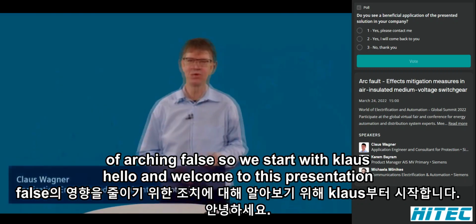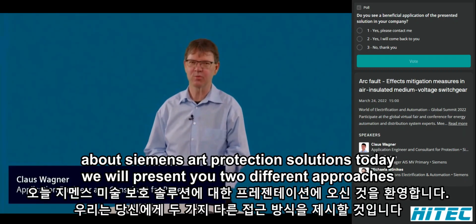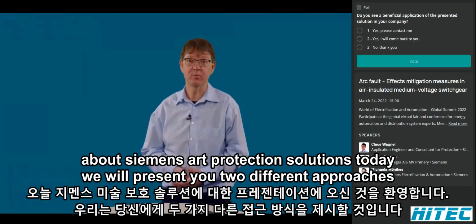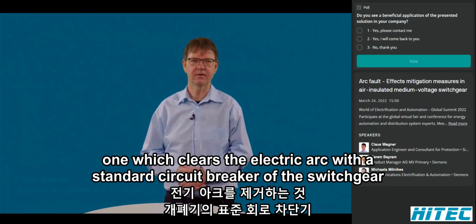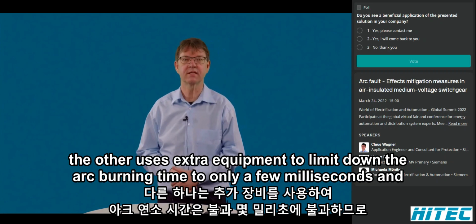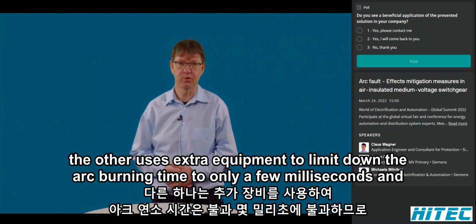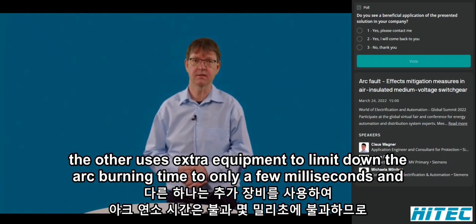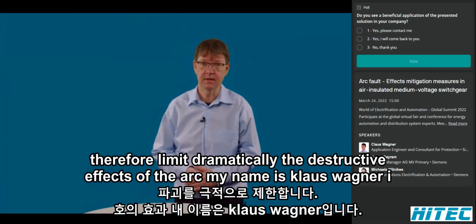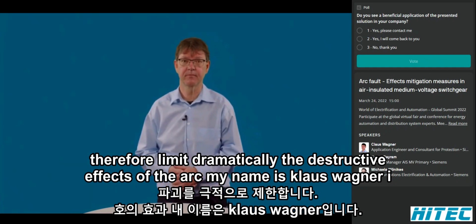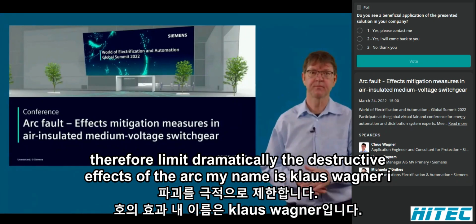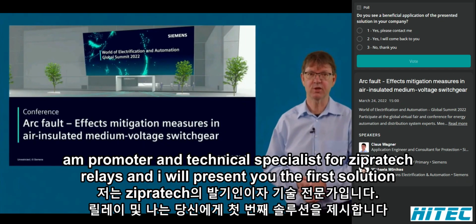Hello and welcome to this presentation about Siemens arc protection solutions. Today we will present you two different approaches. One which clears the electric arc with a standard circuit breaker of the switchgear. The other uses extra equipment to limit down the arc burning time to only a few milliseconds and therefore limit dramatically the destructive effects of the arc. My name is Klaus Wagner. I am promoter and technical specialist for SIPROTEC relays, and I will present you the first solution.